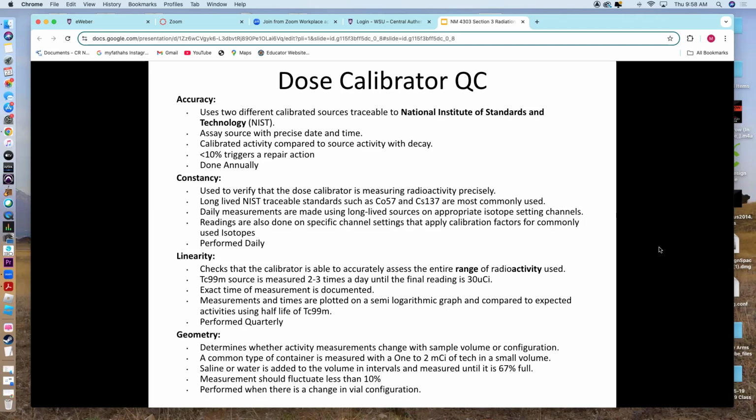And what the computer does is it says, okay, I know what the dose is at this certain time. And then it applies the math, just like you guys have been doing. It does the radioactive decay. And it says, okay, at 3 o'clock and at 4 o'clock and at 5 o'clock and at 6 o'clock, it should measure at this according to the math. And so when you put it in your dose calibrator, you're seeing, is that the case, right? So you might put it in at noon, and you might put it in at 1 or 2, and you might put it in at 5 or whatever. And then you're going to take those 2 or 3 daily measurements and see if the radioactivity or the decay is matched by what the math expects it to be, okay?